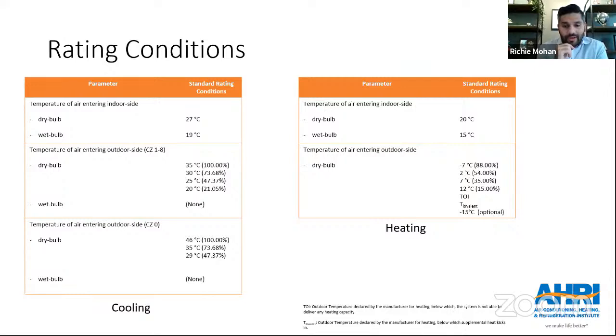Another thing to note is that today we might see an uptick of VRF condensing units being installed with evaporators which may not be from the same manufacturers, through EEV kits. So we need to take a look in the next iteration at how to include those in the scope - whether testing and ratings through EEV kits with a combination of indoor units versus these outdoor units are going to be included in the scope or not. Still a lot of things to expand upon, if not in this iteration, then in the next one.